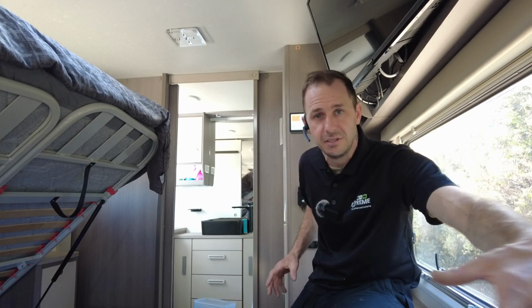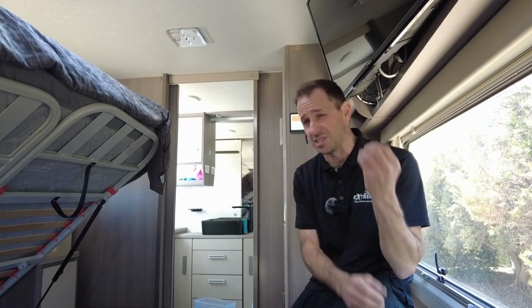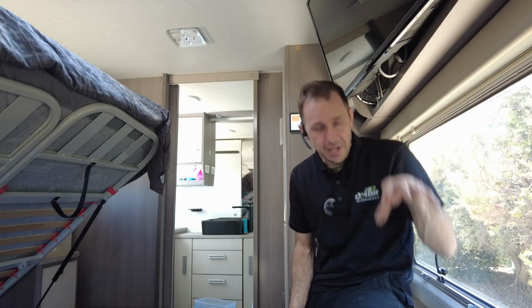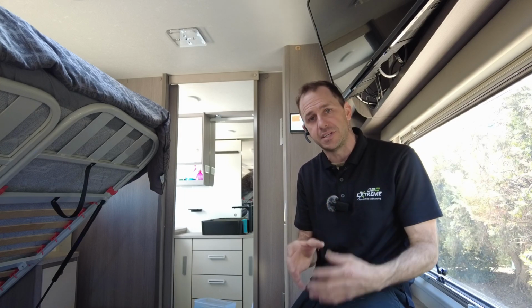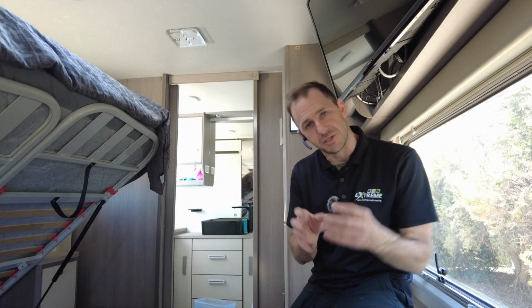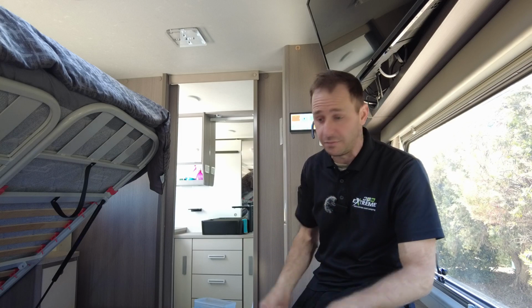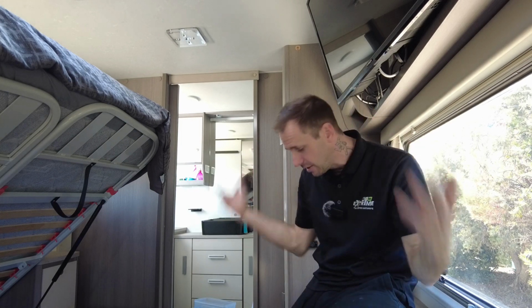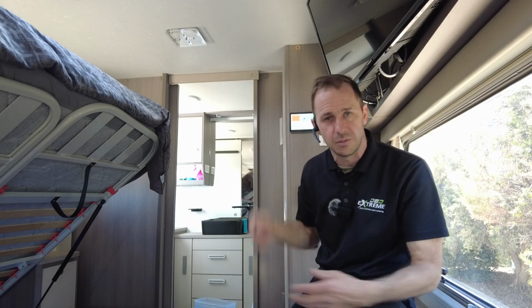It's an outside bin, so ventilation was crucial. So we've got a dual venting system on that, and that's got temperature control as well. That means the fan that controls that enclosure will come on at a preset temperature from the customer. So we've set that box to come on at a certain temperature and off, and it's fully controlled up on this touchscreen or remotely. If he wants to turn the fan on remotely, he can. Not that you do it. My point is you've got control over the complete system with this setup.